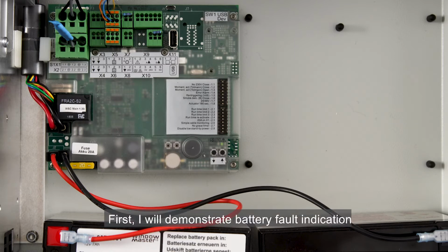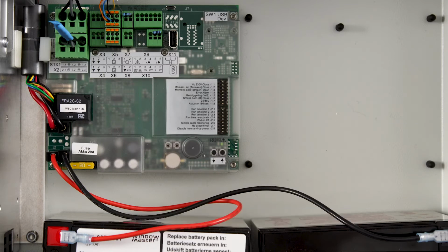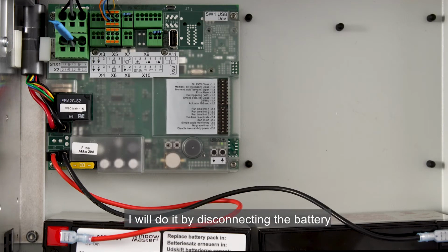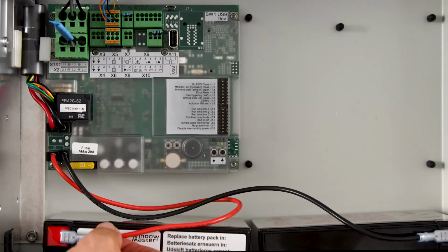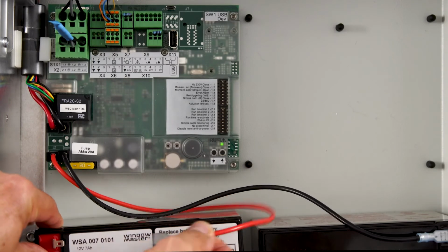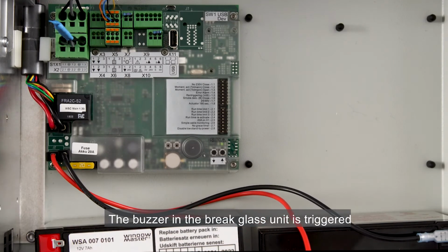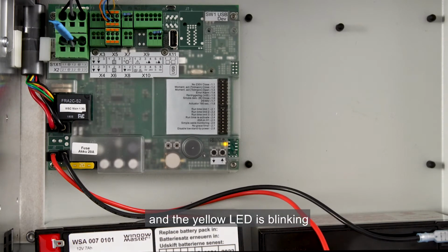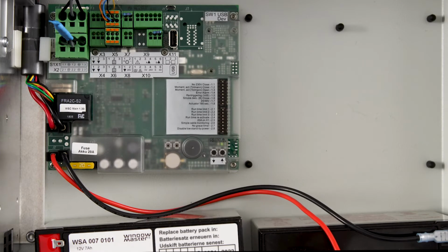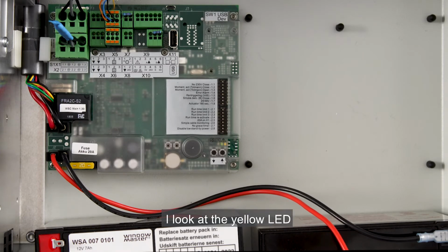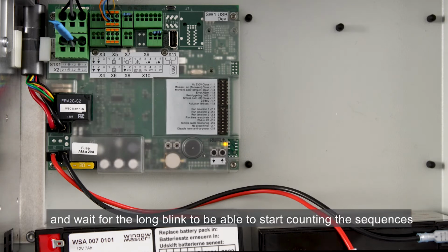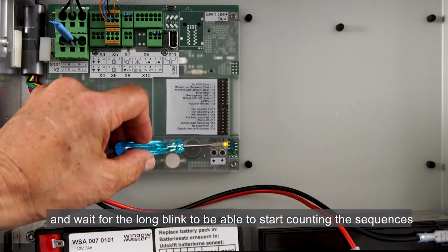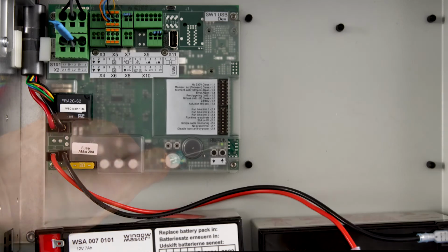First, I'll demonstrate a battery fault indication. I'll do it by disconnecting the battery. The buzzer in the break glass unit is triggered and the yellow LED is blinking. I look at the yellow LED and wait for the long blink to be able to start counting the sequences.